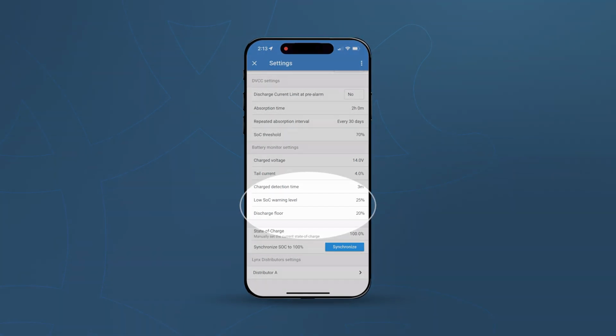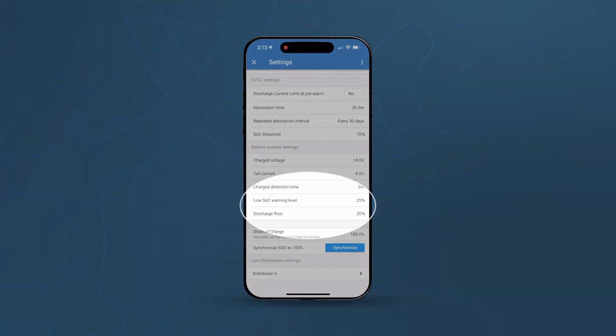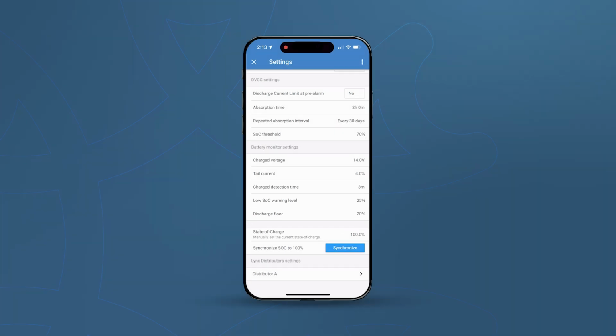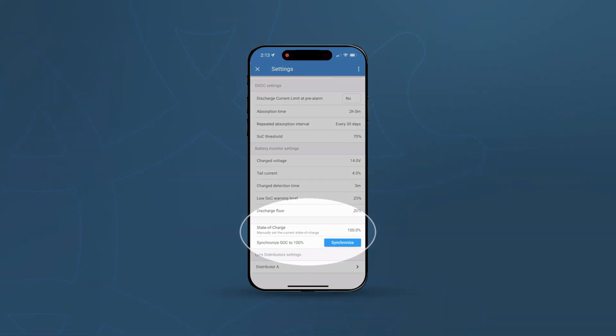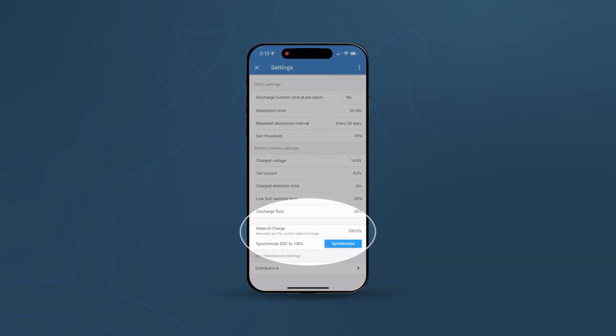However, the low SOC warning level is going to come from factory at 15%, I like setting this to 25%, and the discharge floor is going to come from factory at 10%, I like setting this to 20%. By increasing these, it's going to give you more of a buffer to recover your system from a low voltage event, using easier methods, such as plugging in your inverter charger. The next section is going to be state of charge. I never set this manually, I always let the shunt calibrate this through a full charge cycle.